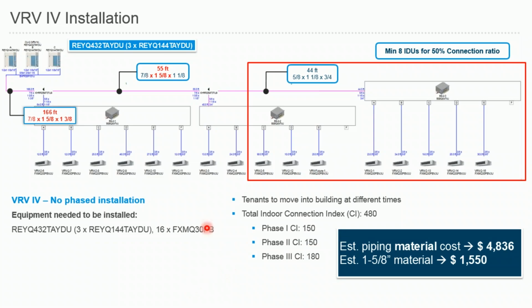The problem here is when you go with the existing rules and VRV4, your final capacity will be forcing you to choose a REYQ 432 model. It's a triple module system. You're still at your first phase of your project, which means you only need 150 capacity index on the indoor unit side. So the problem here is you still need to get to your minimum connection ratio with this system. And we have FXMQ30 model indoor units over here to make calculation easier. I chose FXMQ30 models for each indoor unit.